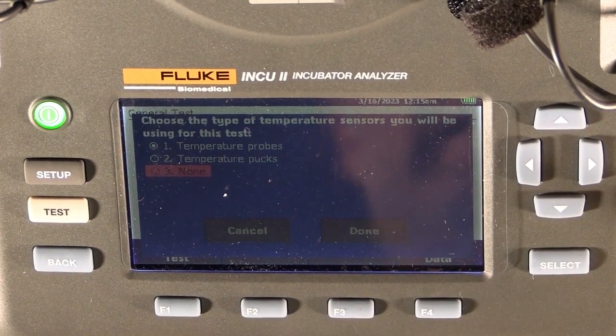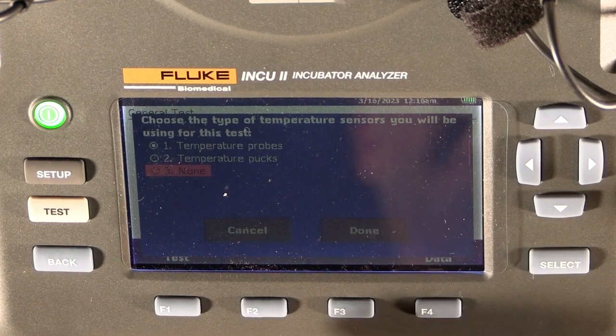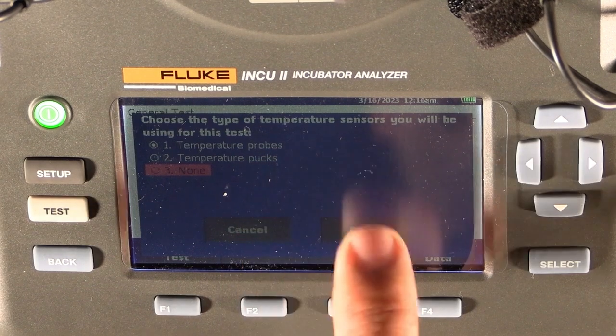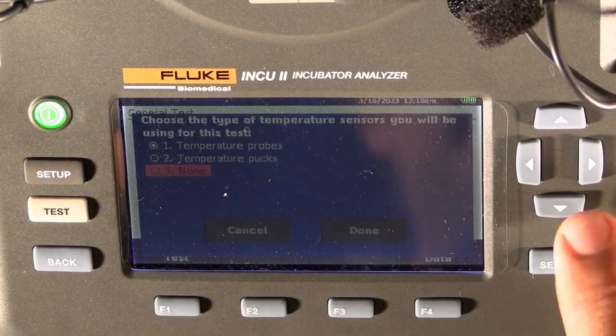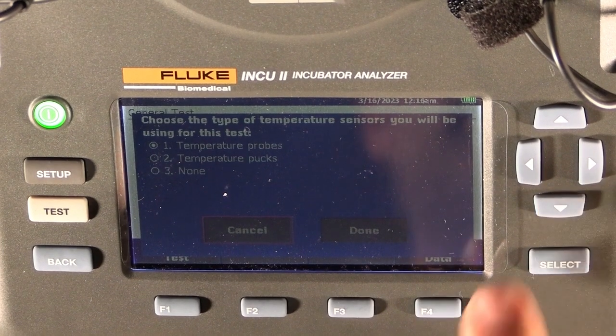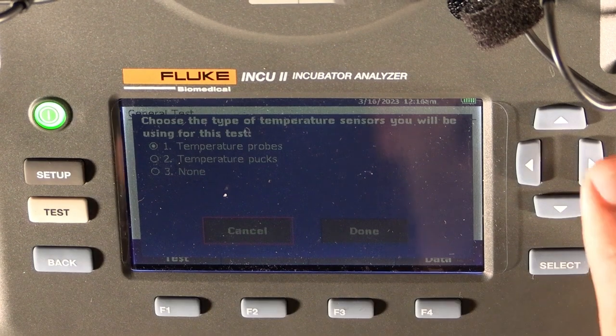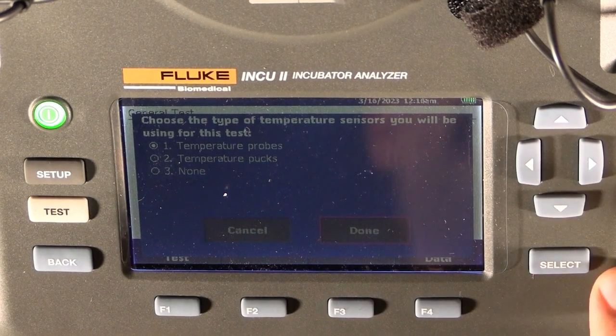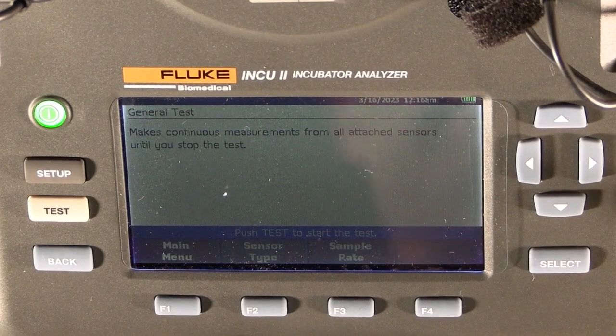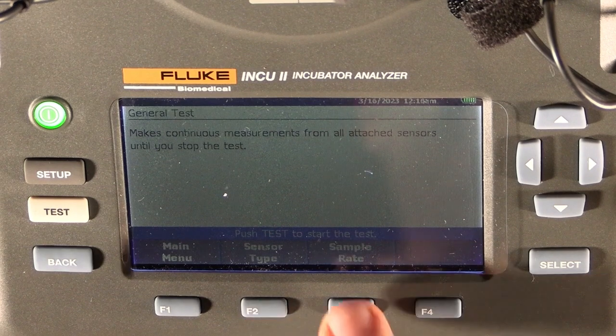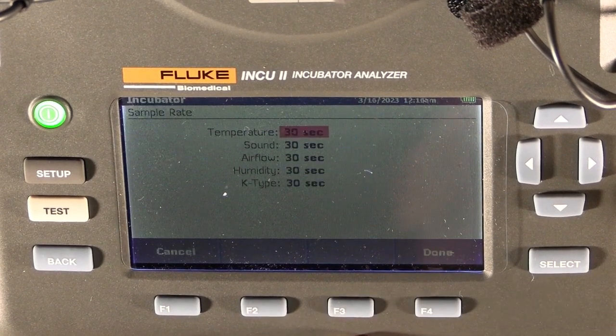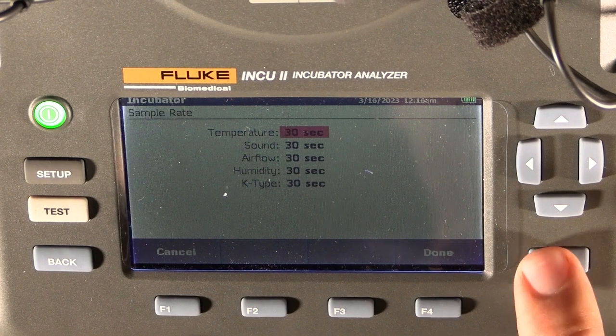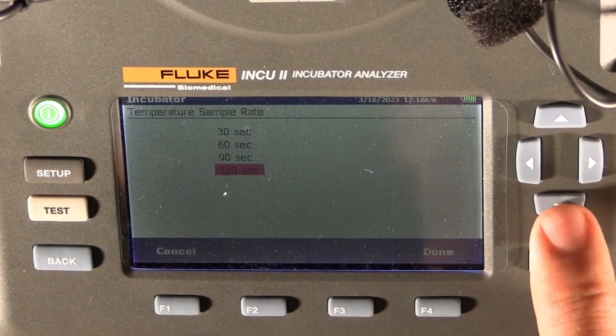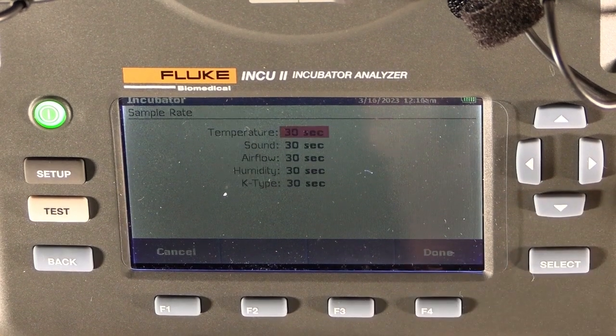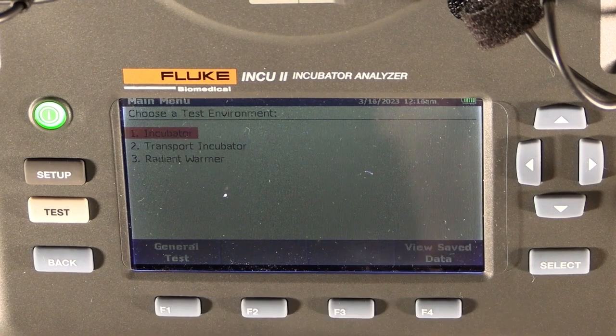Okay, now the trick here is, if we want to get out of this, you'll see that we've got a cancel and a done. But it's not a touch screen. It might be confusing in the beginning. What you'll have to do is go further down with the down arrow until you see the cancel is lit up, and then sideways with the side arrow to go to the done, and then press select. Okay. Then after the sensor type has been chosen, you've got a sample rate, meaning how often must the unit take a measurement. So it can be either 30 seconds, 60 seconds, 90 or 120 seconds. Okay. The standard is 30 seconds. Okay. Go back to our main menu.